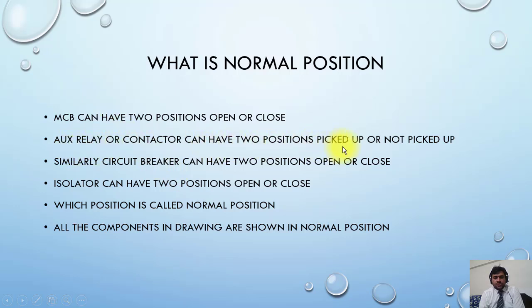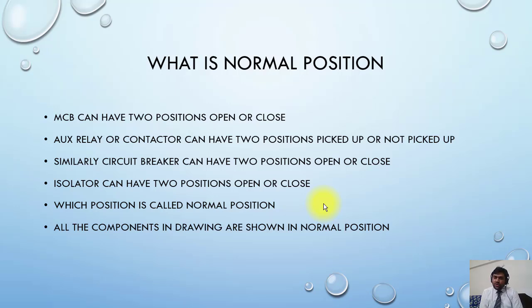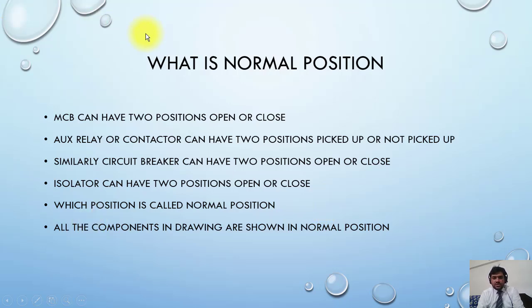An auxiliary or contactor can have two positions: picked up or not picked up. Similarly, a circuit breaker can have two positions: open or close. An isolator can have two positions: open or close. All the components in drawings are shown in normal position. Isolator normal position is open, breaker normal position is open, contact normal position is de-energized.